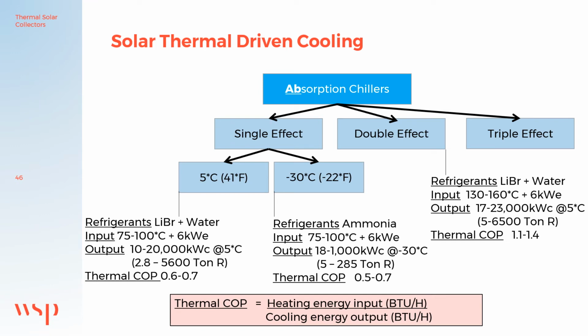The refrigerants that are used in absorption chillers are typically water and lithium bromide, which is like a salt, or water and ammonia. These chillers have been commercially available for the last 6 decades, and the cooling output can vary anything from 10 kilowatt to 23,000 kilowatt, which is 2.8 tons to 6,500 tons, and minus 30 to 5 degrees C, which is minus 22 to 41 degrees Fahrenheit.